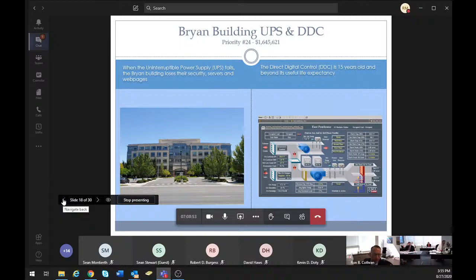For the record, Ron Cochran. Priority number 24 is to replace the UPS and DDC at the Bryan Building. The UPS has had numerous problems over the last 2 years, including bad circuit boards, failure of the backup batteries, and completely shutting down. When the UPS shuts down, building occupants lose internet and security systems, and the public loses access to each division's websites. The DDC controls all heating and air conditioning in the building and will unexpectedly shut down, turning off all heating and air conditioning. The DDC computer and software have been running 24/7 for over 15 years and are so old they no longer support updates and can no longer run on the state security system. Both systems are beyond their useful life expectancy and need to be replaced.